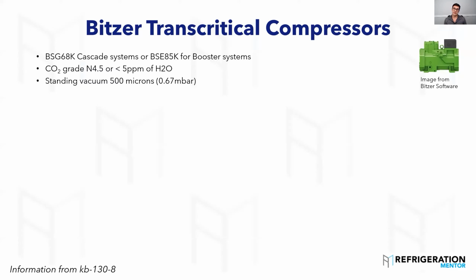Vacuums. You want to get that system down to 500. Bitzer wants you to get down to 500 microns, 0.67 millibar. And I want to get below that. I've been doing a lot of research, actually, to be honest with you. And I'm seeing some people saying 1.5 millibar, which is actually, is it 750 microns per millibar, so it's like 1,000. So I need to look into that a little bit more. Why they're saying 1.5, I don't know if anyone has ever heard that or read that or seen that, but it's a lot higher than the 500 microns that I recommend, and it should even be lower than that.